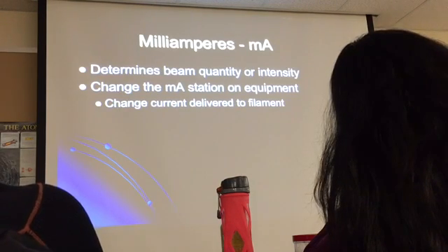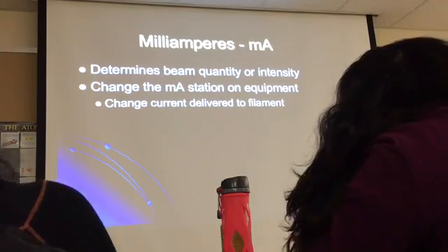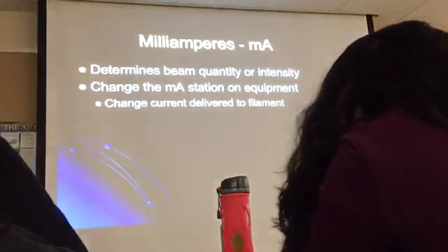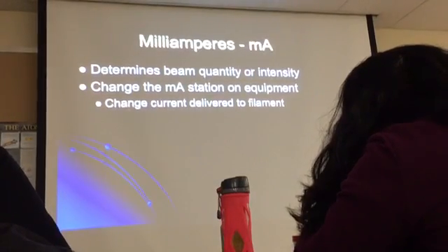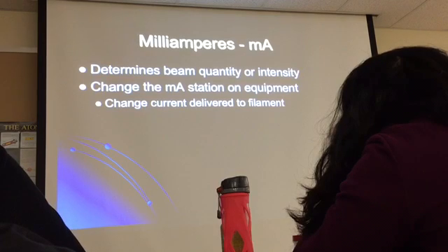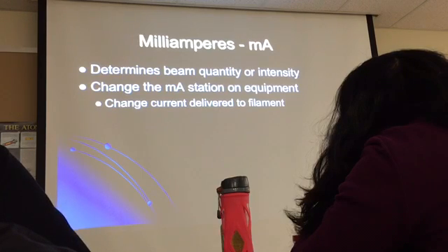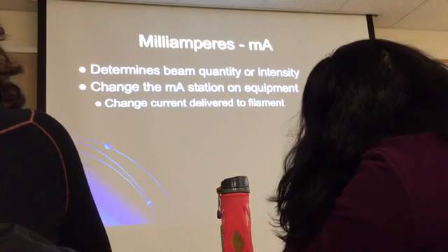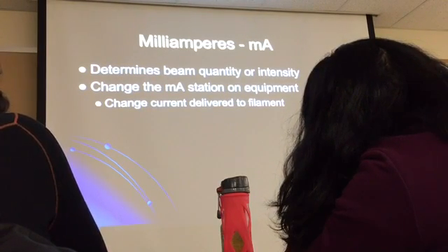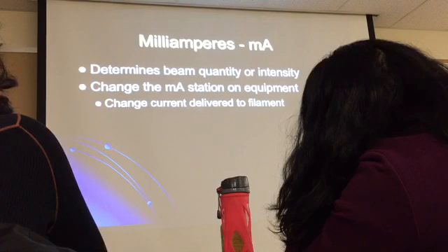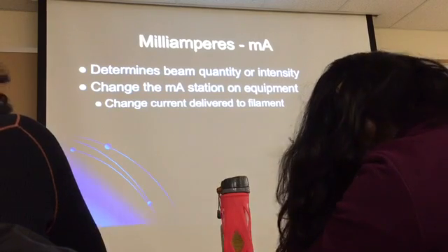Make sense? If I'm at this panel and I want high thermionic emission, I want to increase the current through the filament. There's no amps here, you can look everywhere. All I have is a choice for milliamps, so it is one switch that will change. This is mainly what you're changing. However, changes here affect the amperage that you're using here. Okay? Yes? Good.